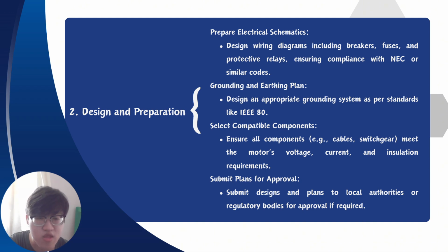It can avoid a lot of safety issues like electrical shock. Next, select compatible components. Ensure all components meet the motor's voltage, current, and insulation requirements, so that the cables and switchgear are compatible with the wiring. Then, submit plans for approval. Submit design and plans to local authorities or regulatory bodies for approval if required, to make sure that the standard is fixed to the local code.